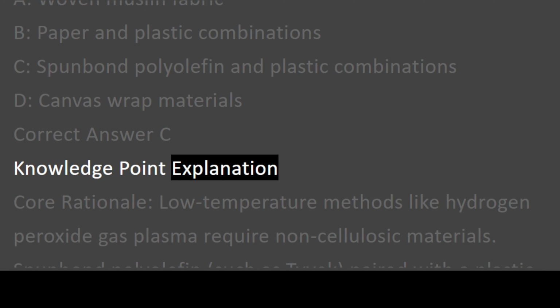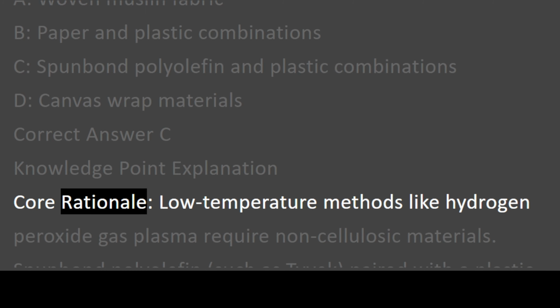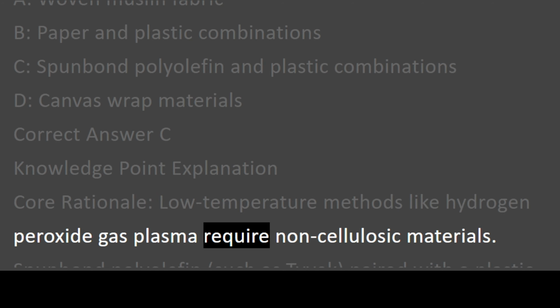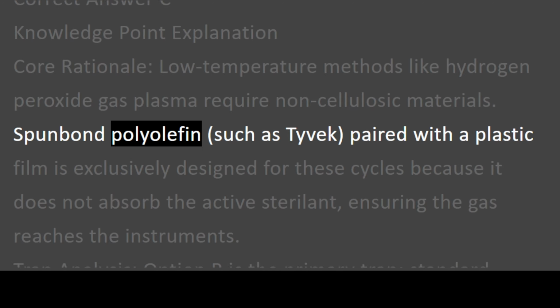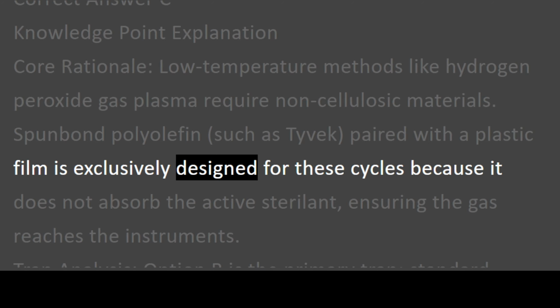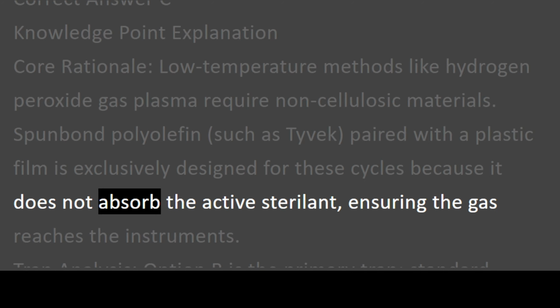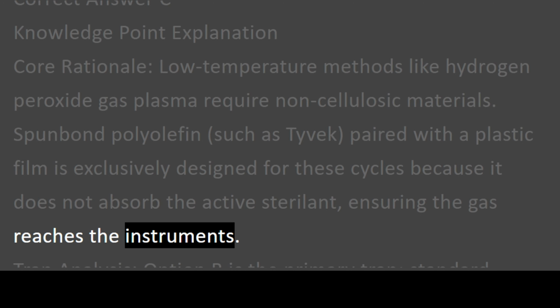Knowledge point explanation. Core rationale. Low-temperature methods like hydrogen peroxide gas plasma require non-cellulosic materials. Spunbond polyolefin, such as Tyvek, paired with a plastic film is exclusively designed for these cycles because it does not absorb the active sterilant, ensuring the gas reaches the instruments.